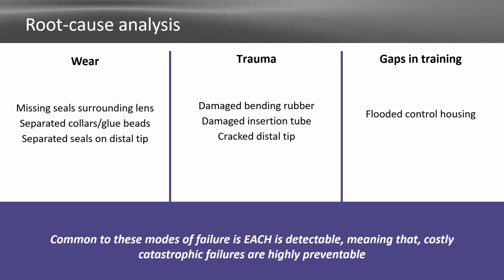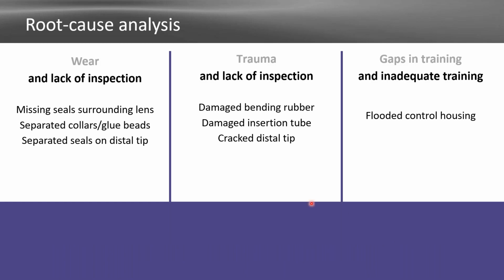So common to all these modes of failure, each is detectable. Even if it's wear and tear, it can be detected if the probe is examined properly prior to disinfection or in between patients. Which means that these catastrophic failures of fluid invasion are highly preventable. So we go back to root cause analysis. Wear can cause these missing seals, the separated collars and separated seals, and lack of inspection. So an inspection will catch these things. Same with trauma. An inspection will catch damaged bending rubber, insertion tubes, or the cracked distal tips. And then the inadequate training, of course, is the root cause for the flooded control housing.